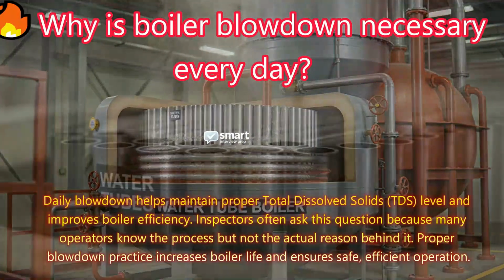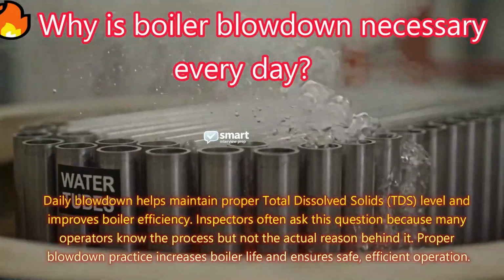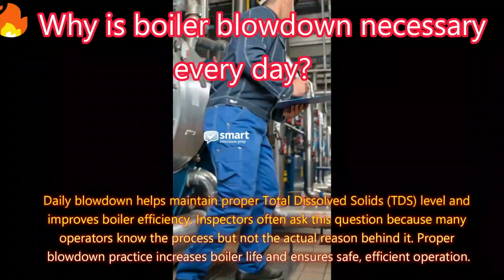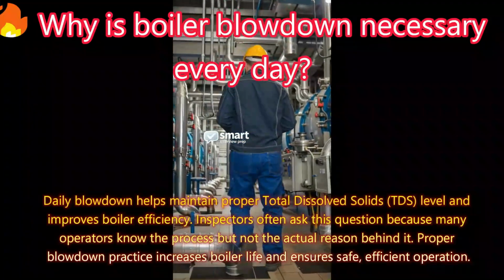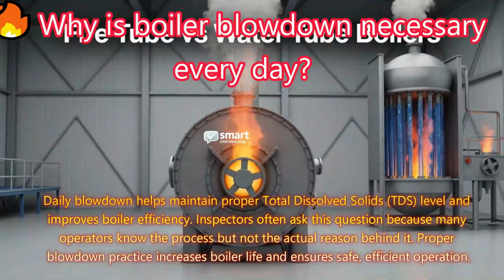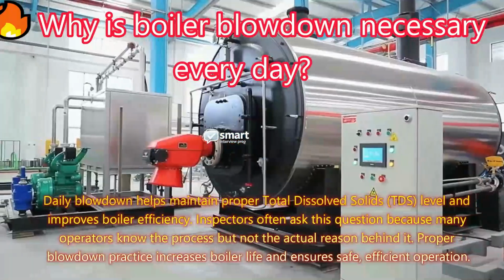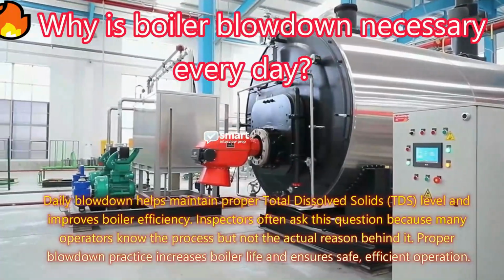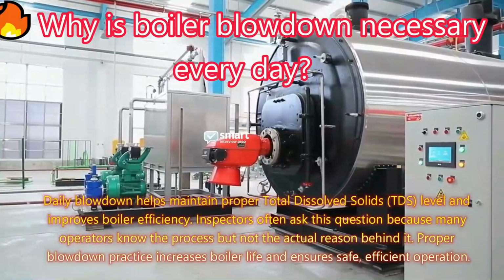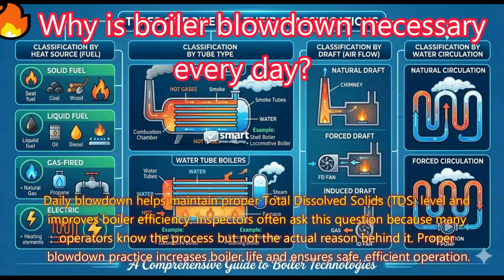Daily blowdown helps maintain proper total dissolved solids, TDS, level and improves boiler efficiency. Inspectors often ask this question because many operators know the process but not the actual reason behind it. Proper blowdown practice increases boiler life and ensures safe, efficient operation.